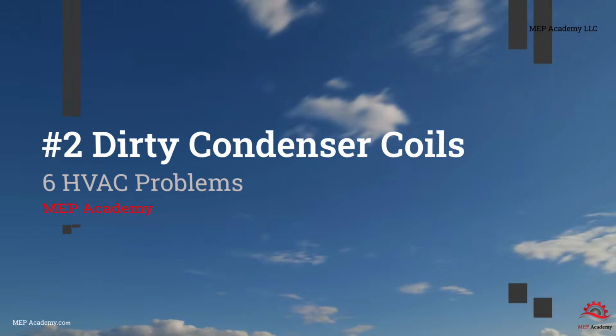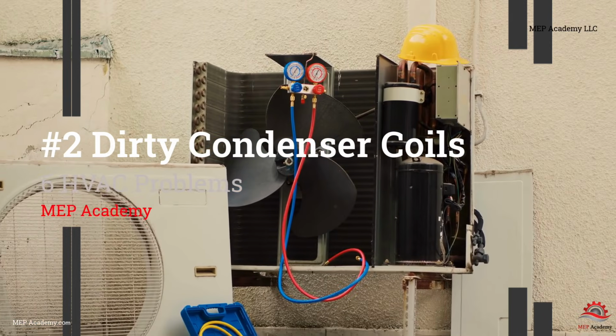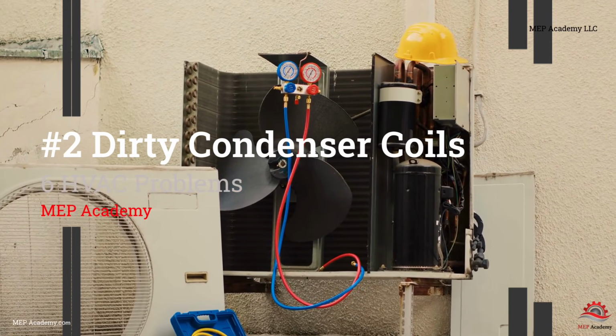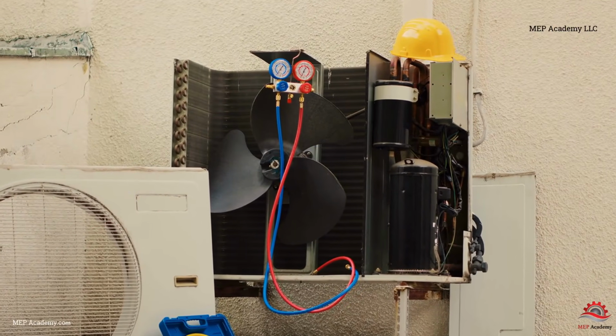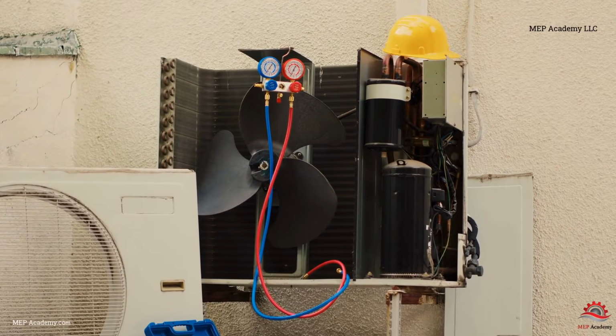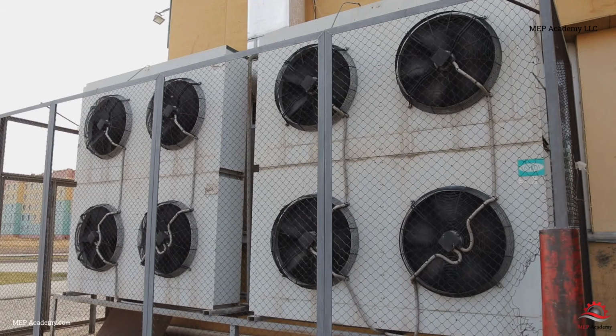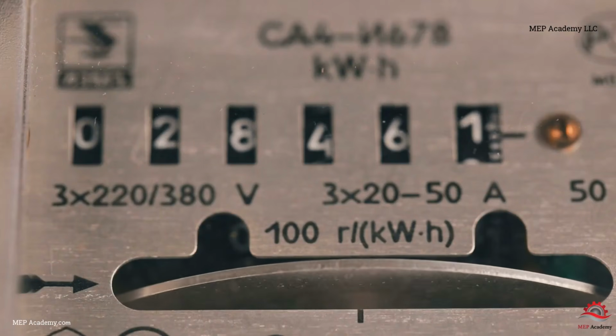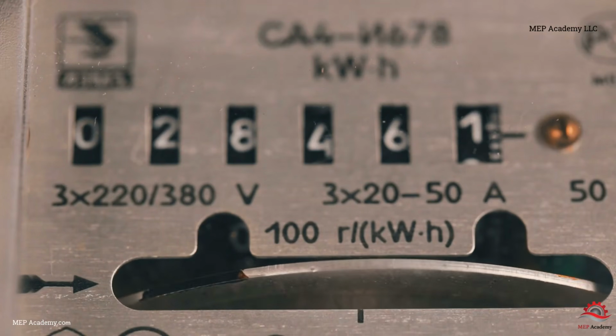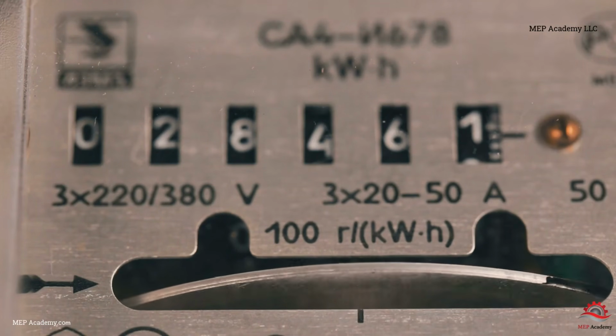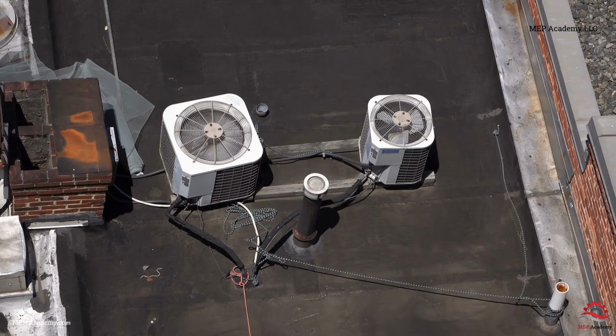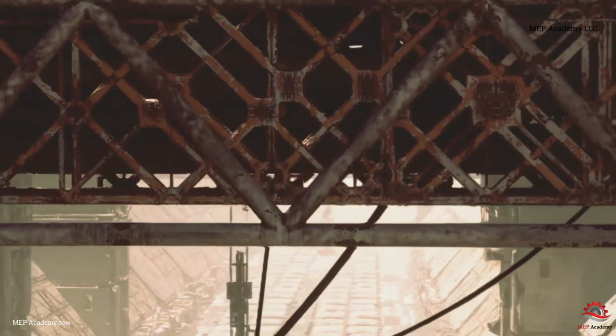Now let's move outside. The condenser coil is responsible for rejecting heat absorbed from the building. Think of it as the radiator of the air conditioning system. When dirt, dust, grease, or debris accumulate on the condenser coil, the system struggles to release heat. Head pressure increases, compressor amperage rises, cooling capacity drops, energy consumption increases. The equipment may still run, but it becomes increasingly inefficient.